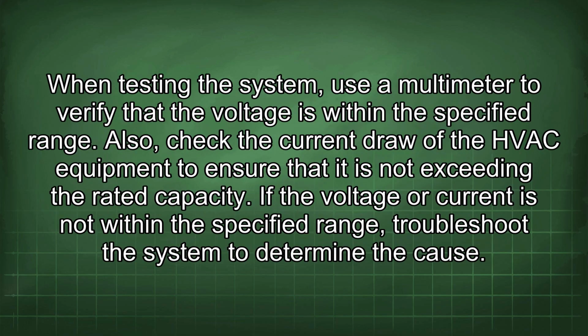When testing the system, use a multimeter to verify that the voltage is within the specified range. Also, check the current draw of the HVAC equipment to ensure that it is not exceeding the rated capacity. If the voltage or current is not within the specified range, troubleshoot the system to determine the cause.